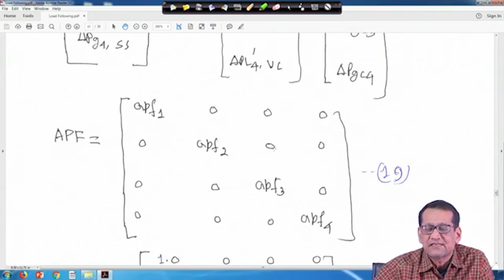Therefore, as I told you, delta PL1 dash UC is 0.005 per unit megawatt, which is demanded by distribution company 1, but all the others, delta PL2 dash UC, delta PL3 dash UC and delta PL4 dash UC, are equal to 0. So if you use equation 18, your delta Pg1 SS will be APF 1 into delta PL1 UC plus delta PGC1. Delta PGC1 is 0, so delta Pg1 SS is equal to 0.005 per unit megawatt, as I told you.